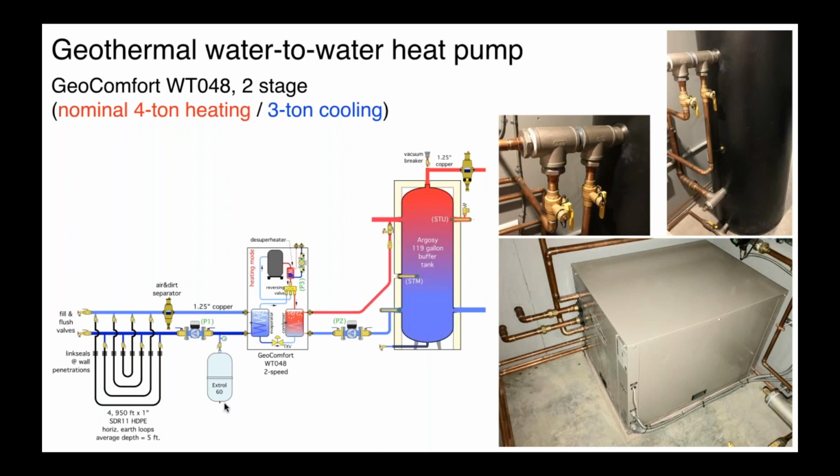And if that happens, that's where the pressure will drop essentially immediately and instantly, and you could cavitate the pump. I actually have got some math on that. If anybody's interested in it, you can make calculations on it. But I would say from a practical standpoint, just pump a little extra fluid into that.